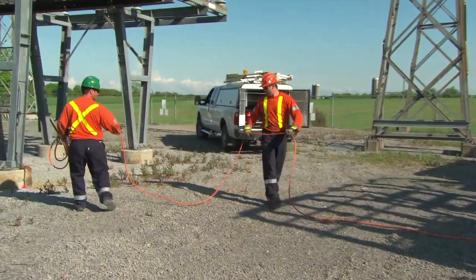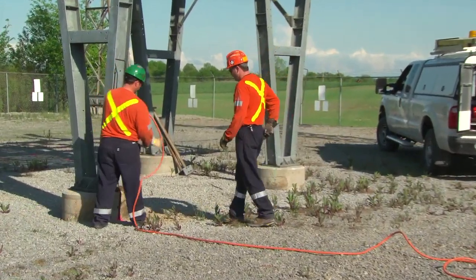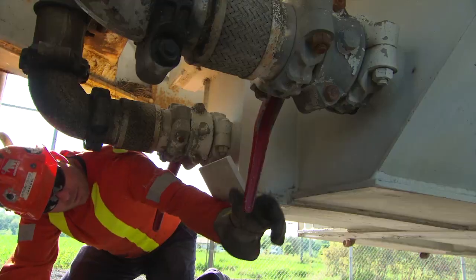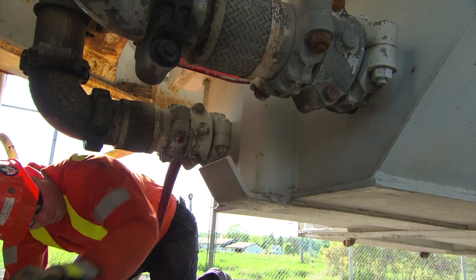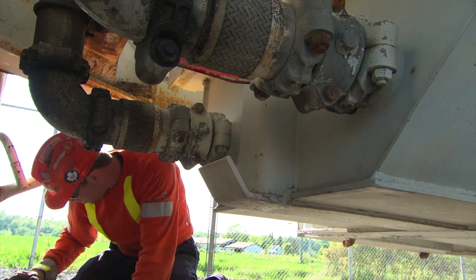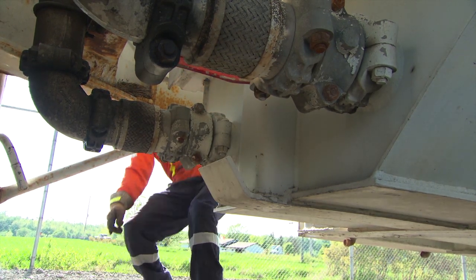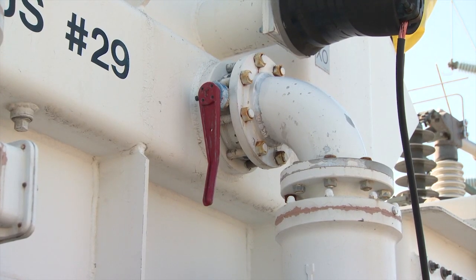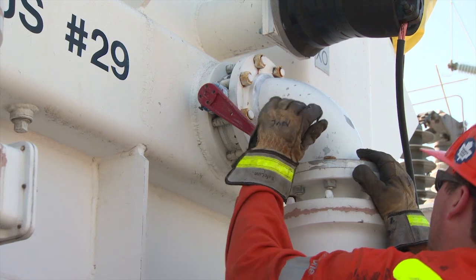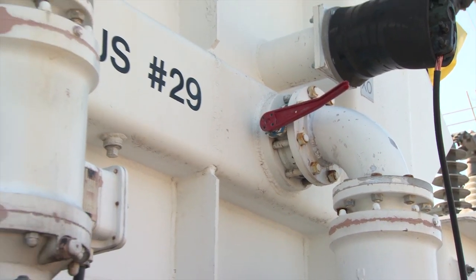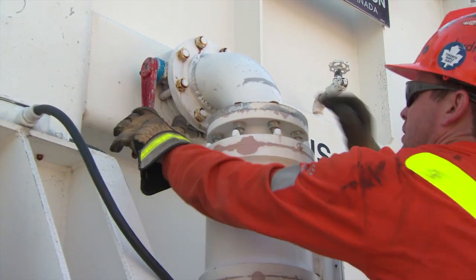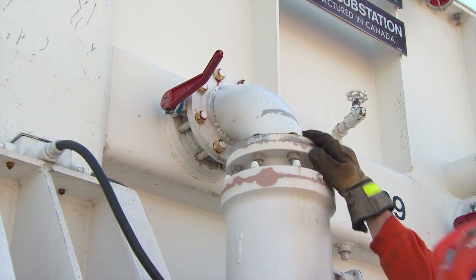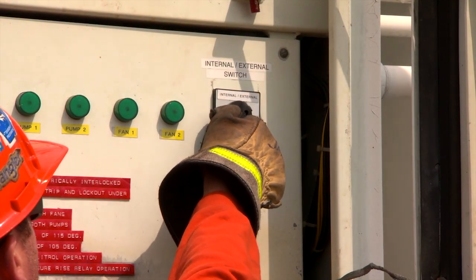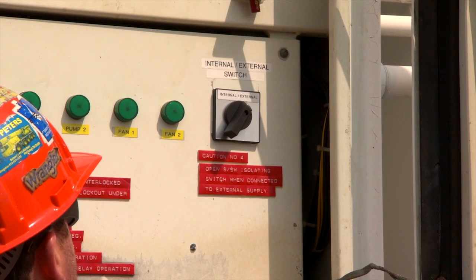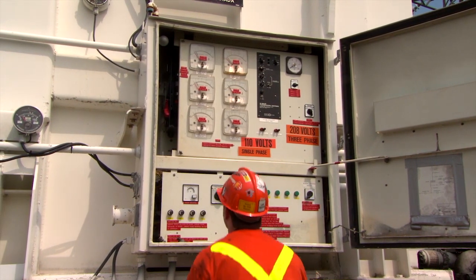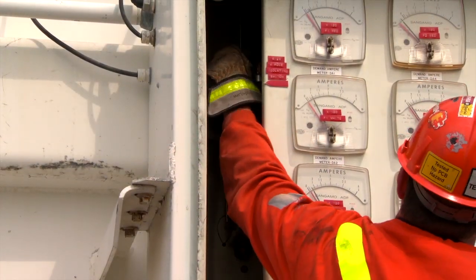Once the tractor has left site, ground the MUS to the station ground using a temporary portable ground. Open the transformer cooler oil valves and breathers. Some mobiles will also be equipped with a 1-inch equalizer valve that needs to be closed. Ensure that the internal-external supply switch is in the external position. Check that the isolating disconnect switch is in the open position if equipped.